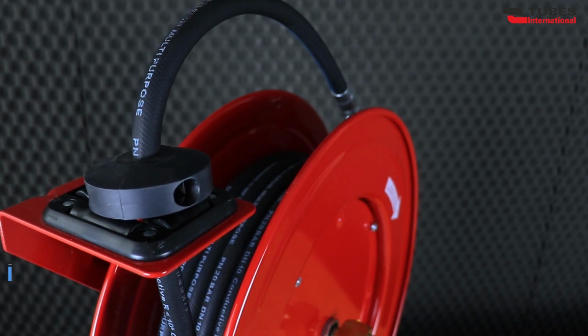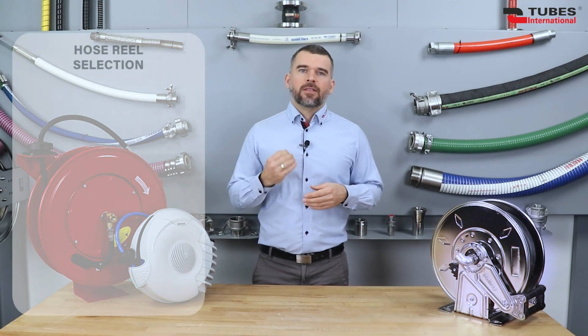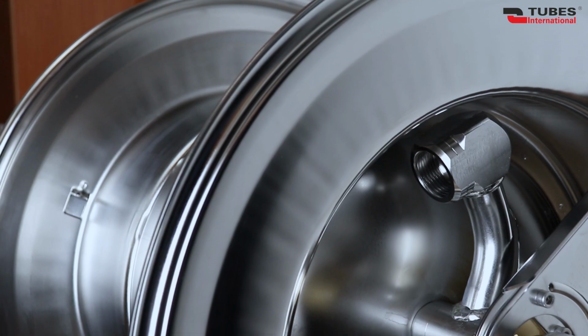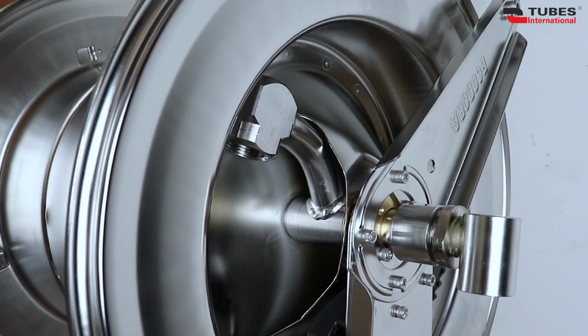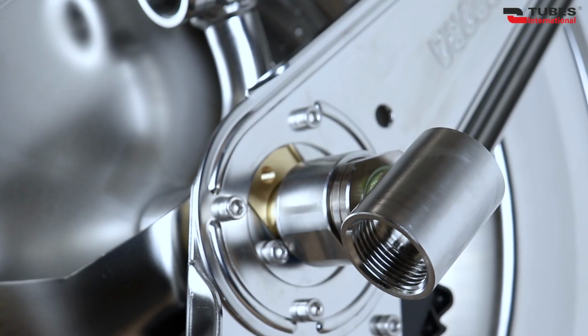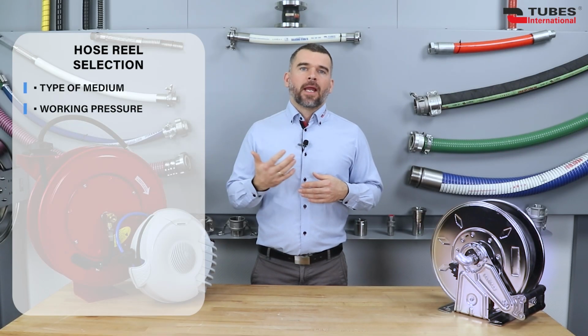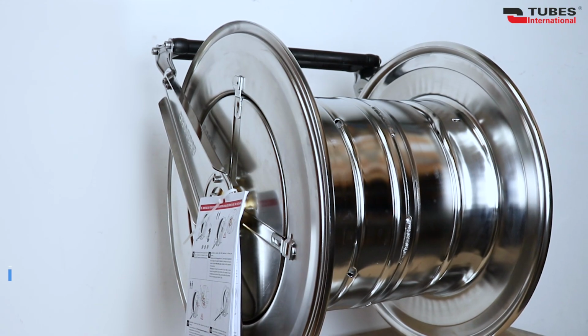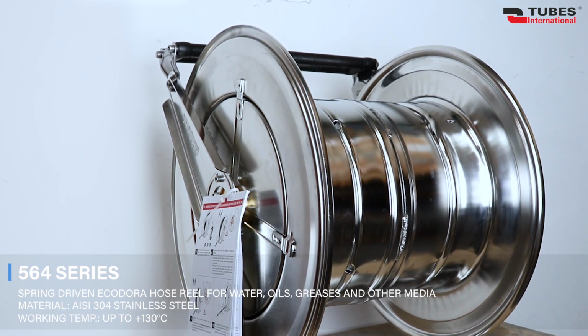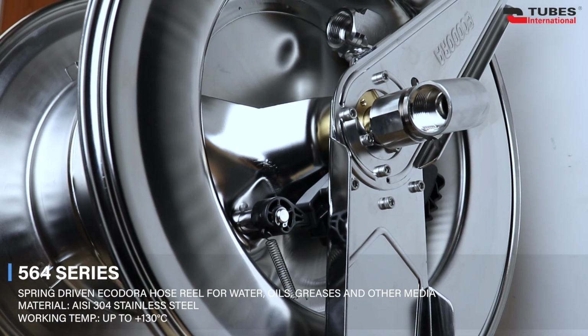Now that we know the benefits of using hose reels and understand their construction, it's time to choose the right reel for us. What should we consider? What factors are important? It is necessary to determine the type of medium the reel will handle. For example, aviation fuel requires a flow path made of stainless steel or aluminum. Operating pressure. The maximum value determines the mechanical strength requirements of the reel. Internal and external operating temperature. For steam reels, it is necessary to use sealing materials resistant to high temperature.